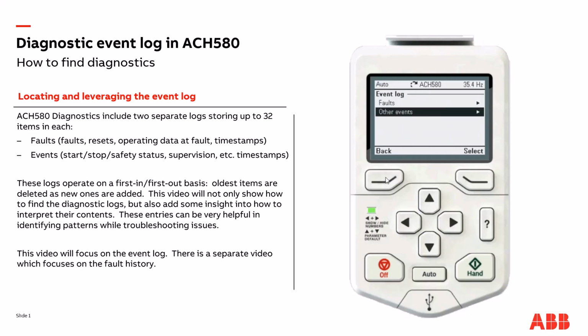And this time let's open up a safety while we're running. So, okay, we get the interlock warning. Okay, how does that look in the event log? Okay, modulation started, then the start interlock opened, and we can see, again, that the timestamp is great here because we can see the whole sequence of operation. Okay, so now I will make the safety again, and we'll start again. Again, you can see that sequence of events in here.